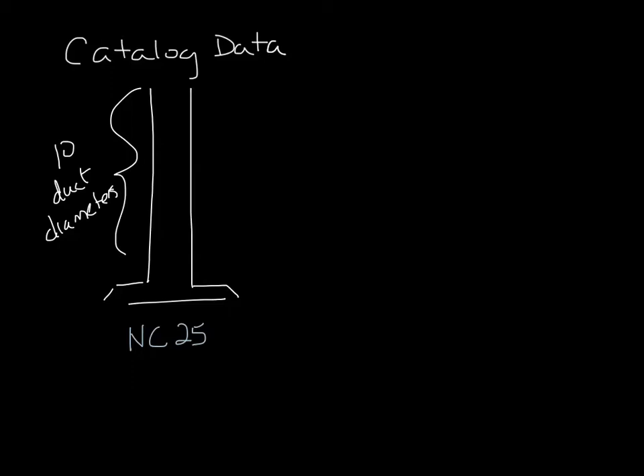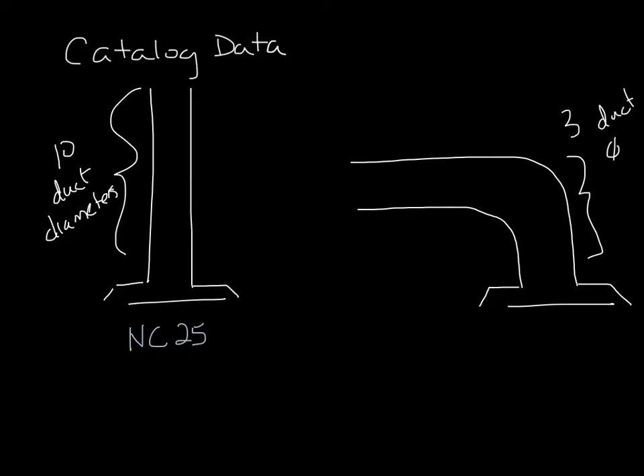The best installation would have 3 equivalent duct diameters going into the inlet with a 90 degree radius of flex duct. Even this installation will add 1 NC over catalog data. So in this installation, our NC25 catalog diffuser would actually sound like NC26 installed.